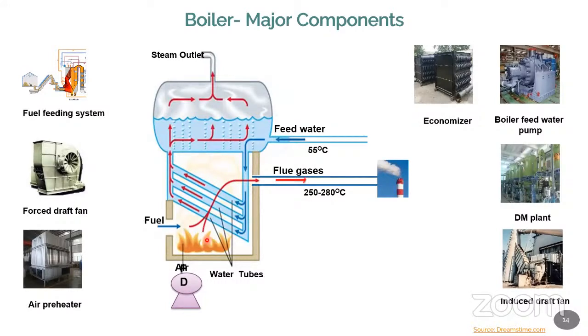So in three different ways, you can achieve energy conservation. Number one, you can take the flue gas and heat up your feed water, that is called an economizer. Then you can pass the flue gas on to your wood, that will remove the moisture. And you can use the flue gas to heat the air also. The incoming air, with the help of an FD fan, you can heat that also. That's called an air preheater. There is a separate equipment called the air preheater, APH. So you can use this flue gas heat to preheat the air. That is also very important because we need a temperature, the 3T, one T is the temperature to be put inside the chamber. So that's another point. Always remember, this is called APH, air preheater.